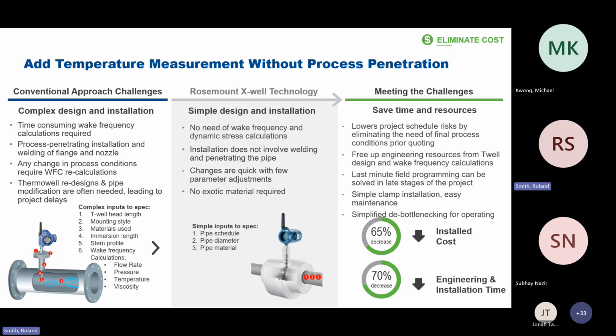So very important. You don't want a thermowell end up going through your turbine. Trust me, that's not a good scenario. So we've come up with X-Well technology where we enter the pipe schedule, pipe diameter, and pipe material. We insulate 6 inches before and 6 inches after to reduce the stem temperature influence to very accurately measure the temperature of gas or liquid in a pipe. So we can make that measurement very accurately without penetrating the pipe.